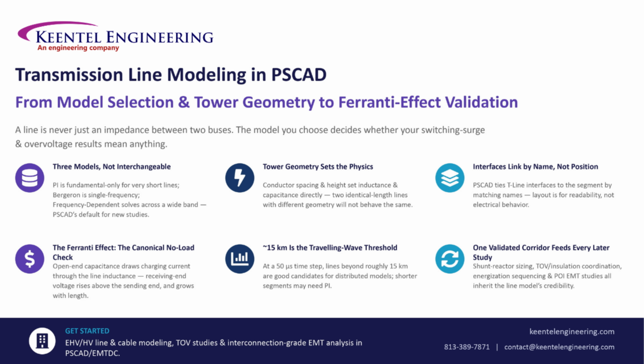Getting the model type right isn't enough, though. Tower geometry sets the actual physics, since conductor spacing and height directly determine inductance and capacitance. 2 lines of identical length with different geometry simply won't behave the same.